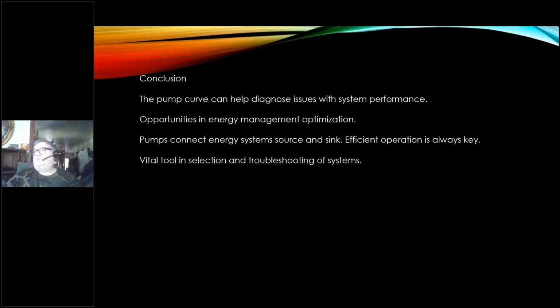So I hope you can readily see, or at least find something to use in the pump curve to help you diagnose issues with system performance. The opportunities in energy management optimization are right there with your horsepower and flow. The pumps connect the energy system, source and sink. Efficient operation is always key, especially in that last one where I've got all those pumps trying to transfer water from the plant to the building, and it's vital in selection and troubleshooting of the systems.